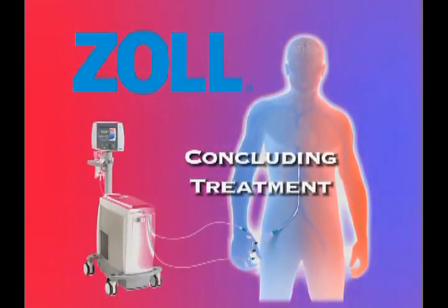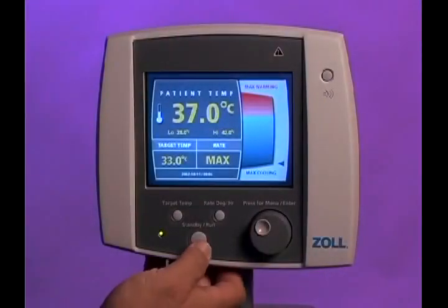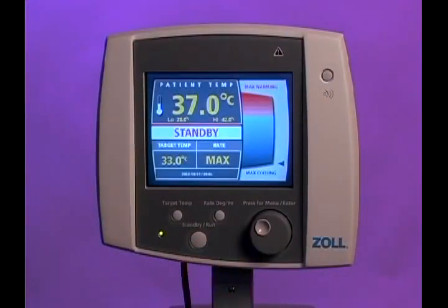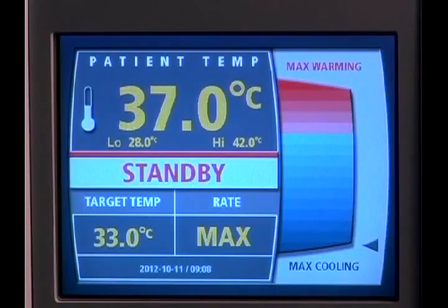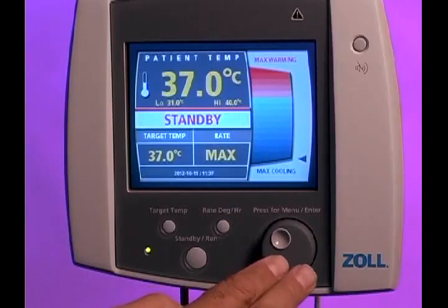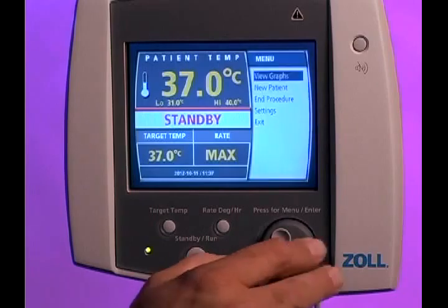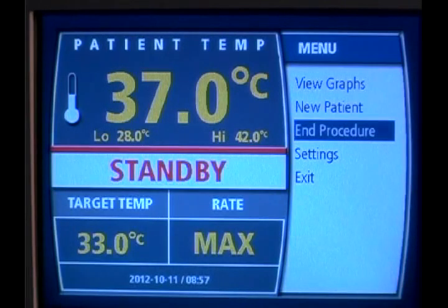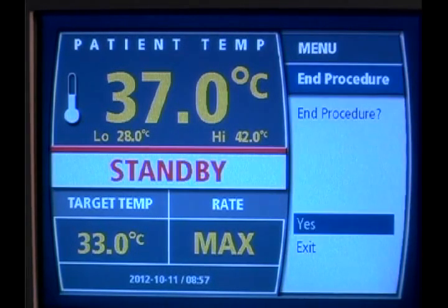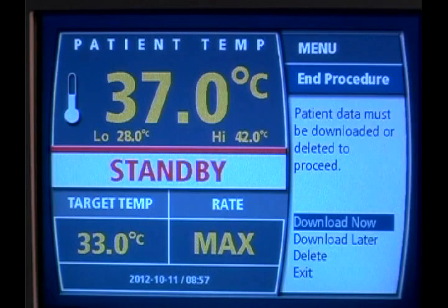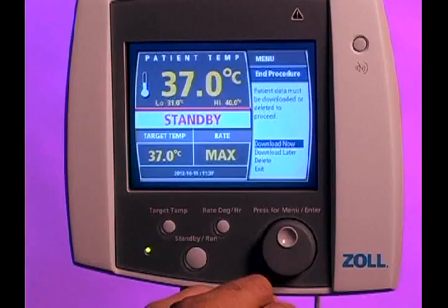At the conclusion of patient treatment, press the Standby Run button. The pump will stop turning and the standby screen will appear. Press the menu controller once and select End Procedure from the menu that appears. The data stored by the Thermogard XP must either be downloaded or deleted prior to beginning your next patient. You may choose to download the data at another time.